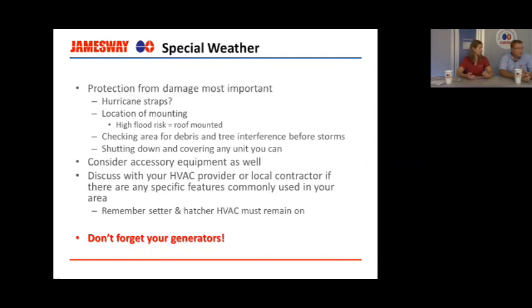Okay, that was one of the questions I had too. A lot of people in the industry are very familiar with multi-stage, and they know that like the back of their hand. So when they move to single stage in a new or existing unit, or modify their existing hatchery, what generalities as far as the change in functioning of the HVAC unit should they expect? So typically your multi-stage unit is going to be oversized for your platinums. In most areas, that's not going to cause a problem. It just means that your dampers aren't going to be open as wide as they are with your multi-stage if you're running an economizer system.